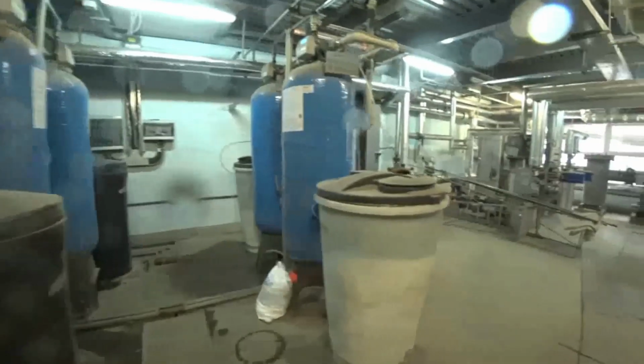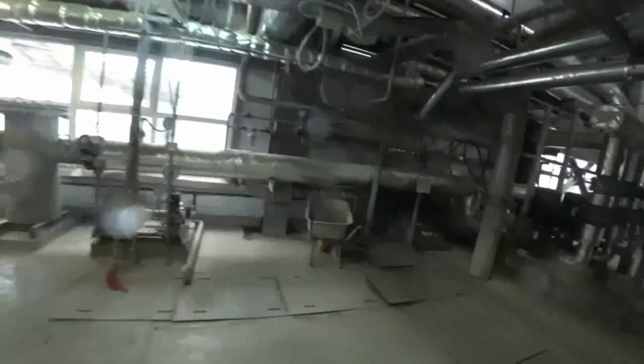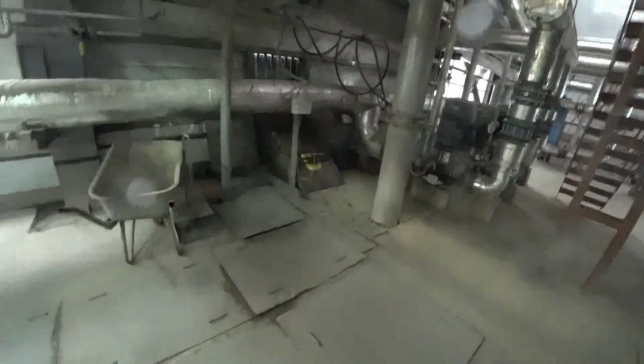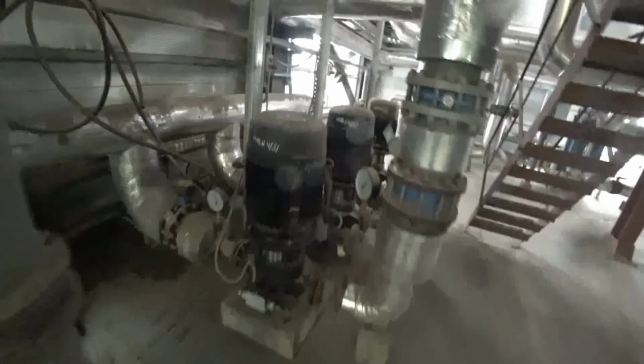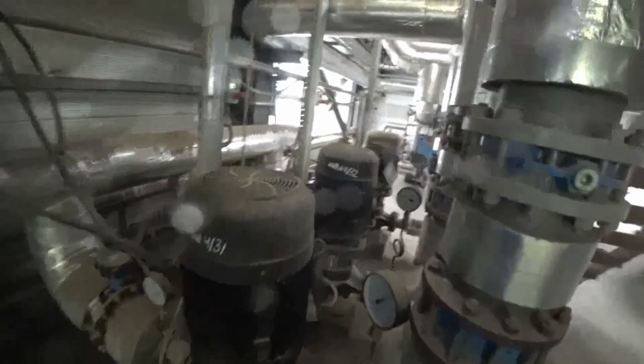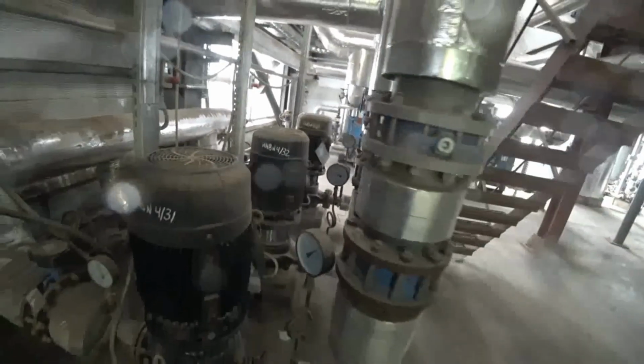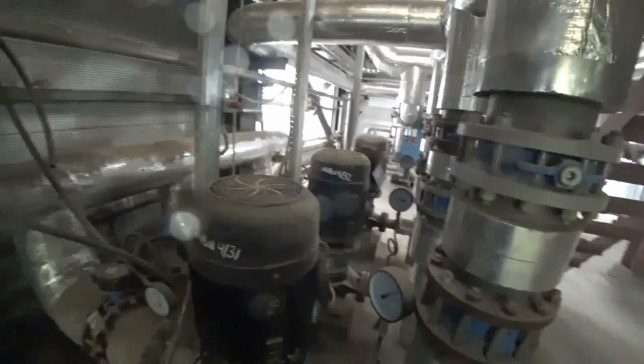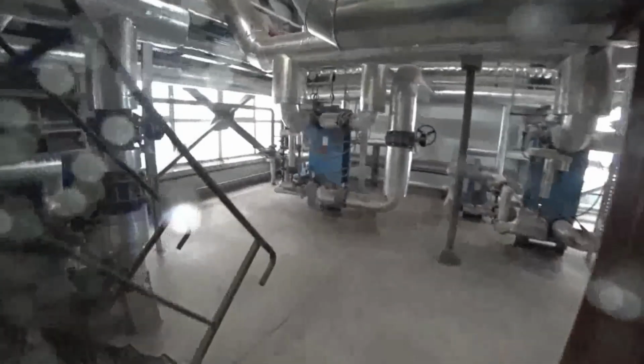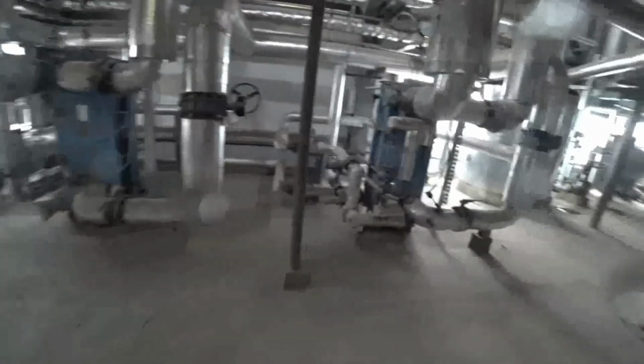Here is the equipment of the water softening plant. Here are the feed pumps of the steam boiler, and here are the network pumps of the poultry farm heating system. 2 working and 1 reserve. The pumps are designed to circulate hot water in a volume of 220 cubic meters with a temperature schedule of 90 degrees Celsius to 70 degrees Celsius.